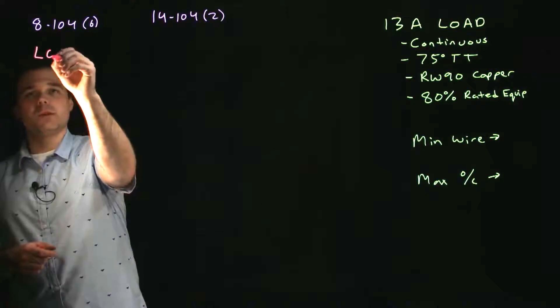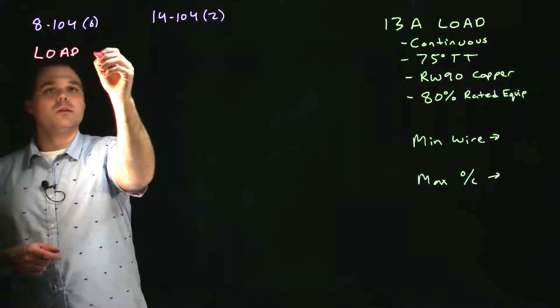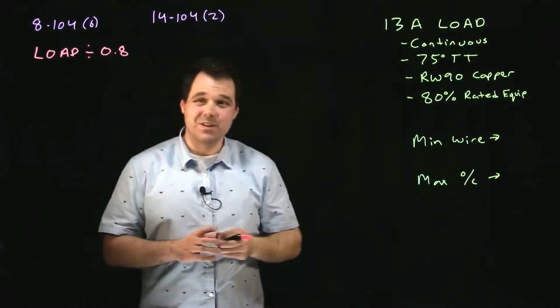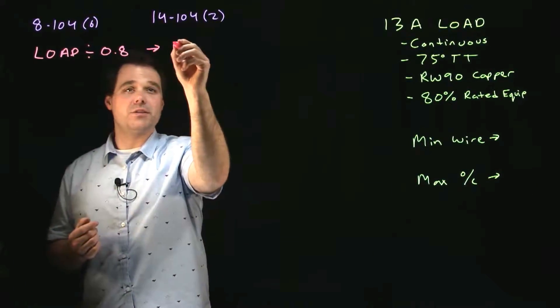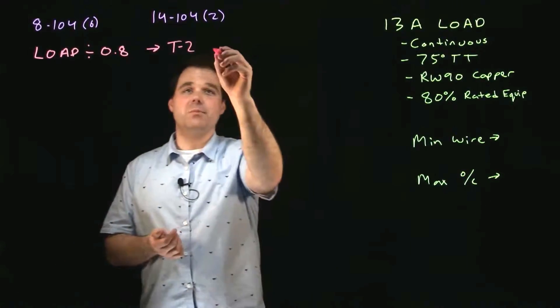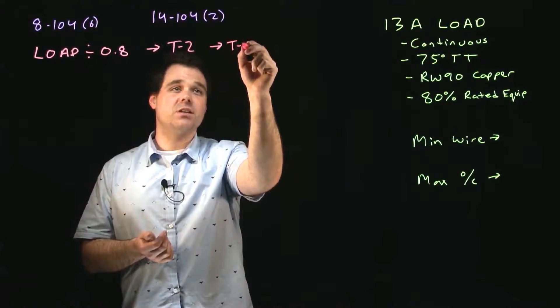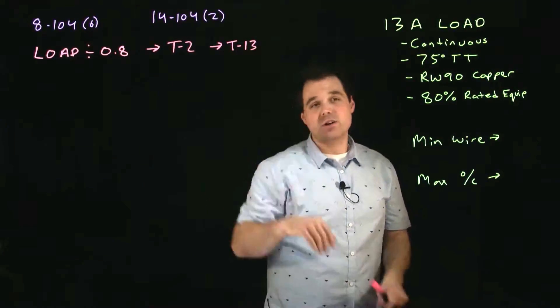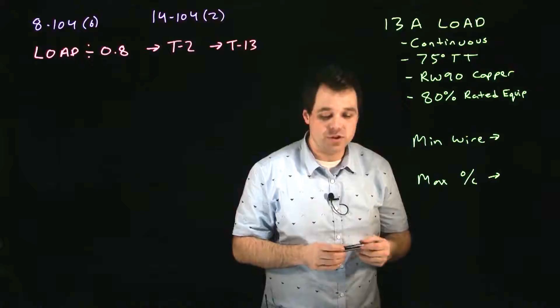So the process is going to be I'm going to take my load divide it by 0.8. Once I do that I'm going to go to table 2 in this case and size my wire. After that I'm going to go to table 13 and size my overcurrent. Now that's the general process we're going to actually see 14-104 sub rule 2 in effect today.